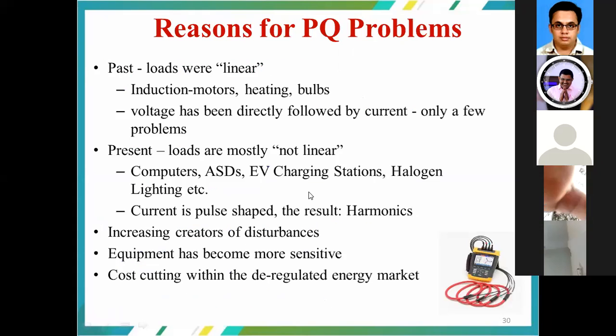And when it comes to the first disturbance, which is sag, sag means the deviation in the voltage, the dip. The starting of heavy loads, that means large motors or EV converter stations of larger capacity, means we are going to encounter the sag at the distribution network. And brownouts, again, if we are not containing the ill effects of the harmonics at the starting point or at the converter station, that is going to lead to brownouts. And fault clearing times of distribution feeders from 5 to 15 cycles, again, is a major concern if you are relying on quality power. And typically the sags range from 20 to 50% depending on the particular distribution network.